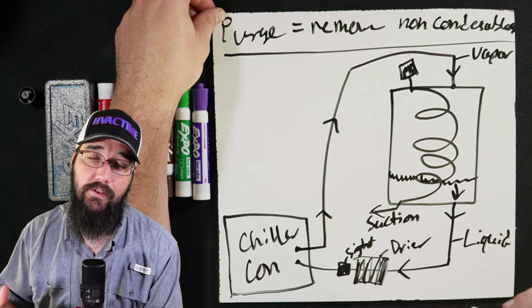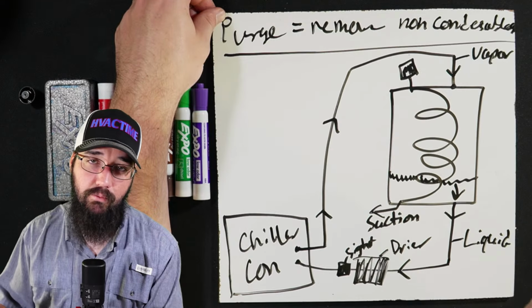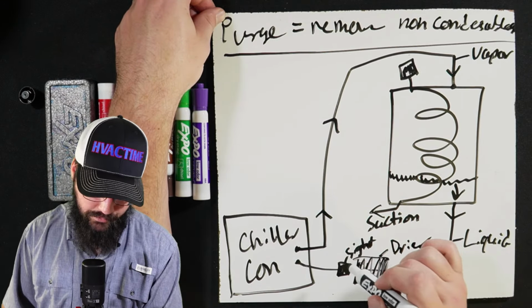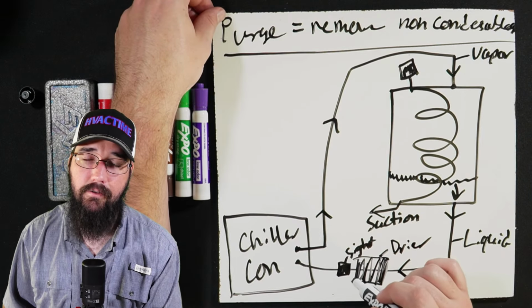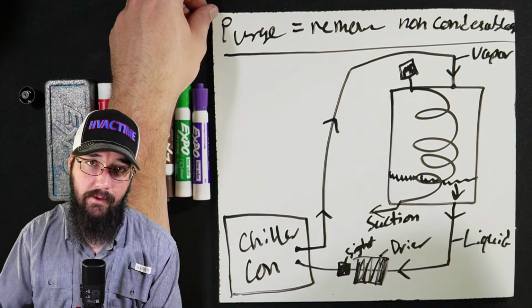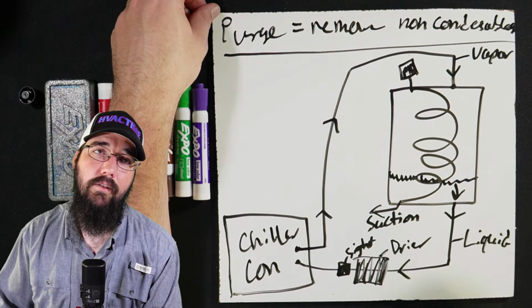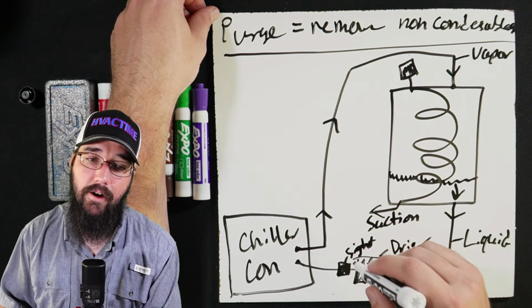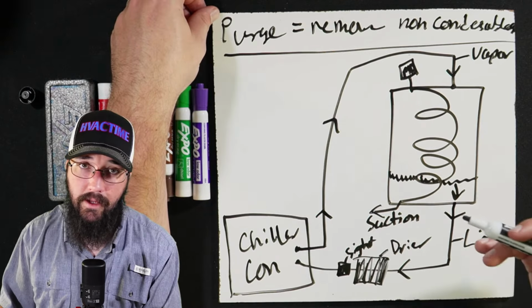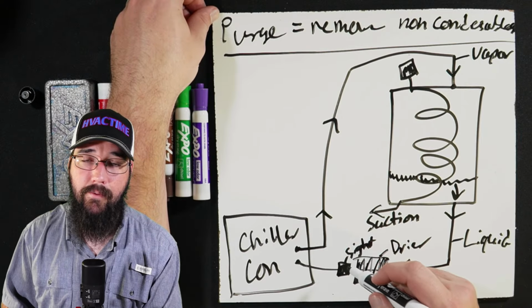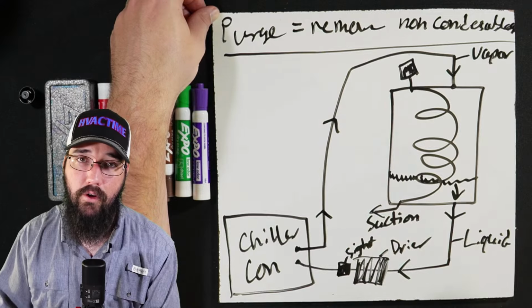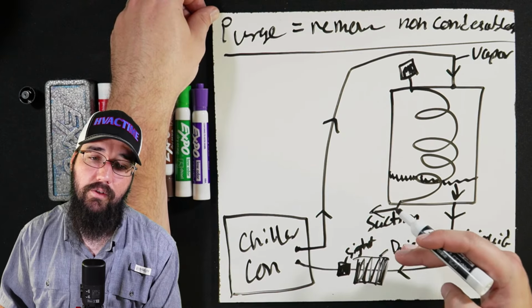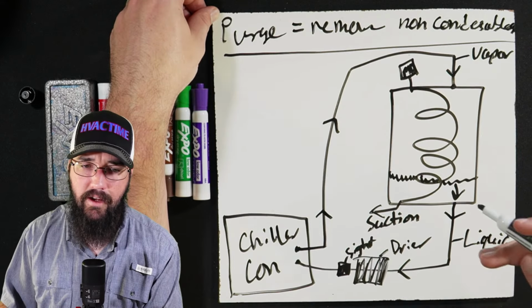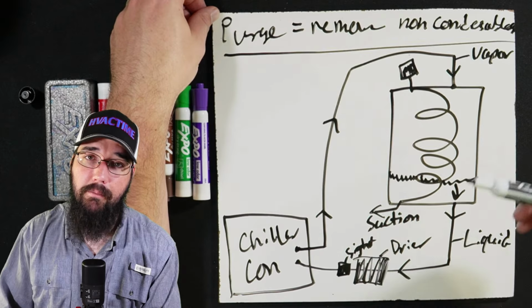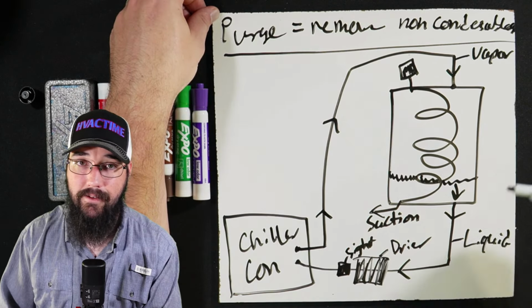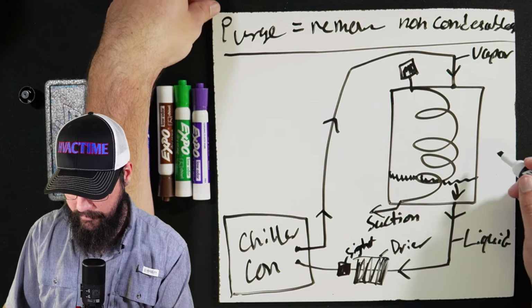If you see that sight glass is showing constantly wet, you need to be increasing your replacement cycle of that dryer, right? So if you see it's showing very wet, then instead of changing this dryer annually, you might want to change it quarterly or semi-annually until you start to see a clean glass or a clean indicator. As it starts to show less moisture, then you can start going back to maybe an annual change, and that'd be perfectly fine. But that is how we're going to make that determination: what does that sight glass say, which most of these systems will have included.